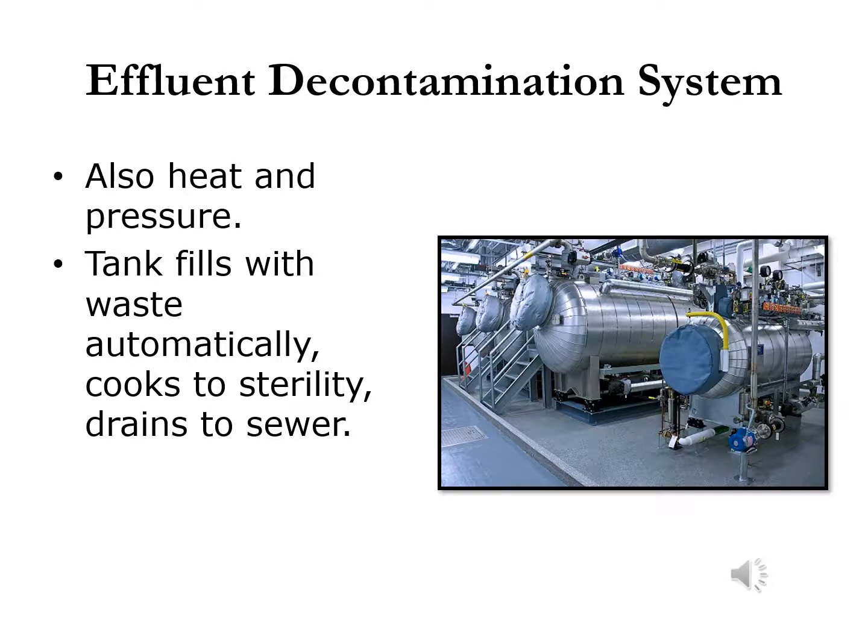And they are used to decontaminate all other waste coming from lab areas: sinks, toilets, drains, water fountains. But the same principle as an autoclave is used. All that liquid is brought into these tanks, brought up to temperature and held for a certain amount of time, and then in sync with the city waste system, it's dumped into the city water.